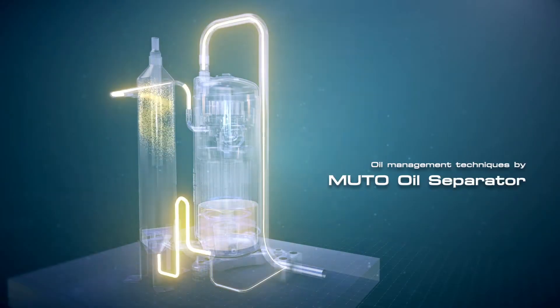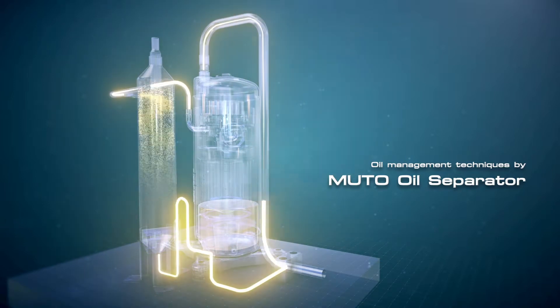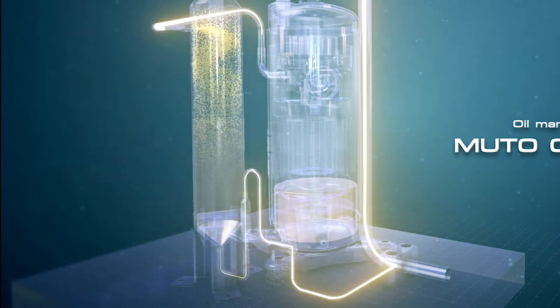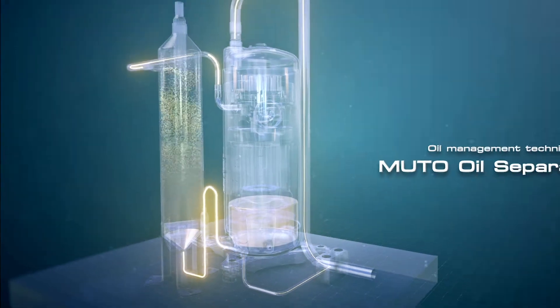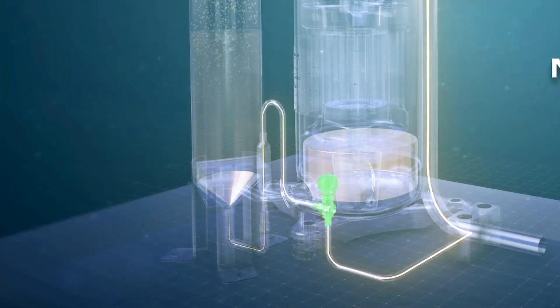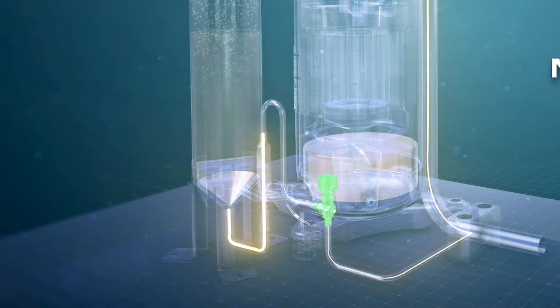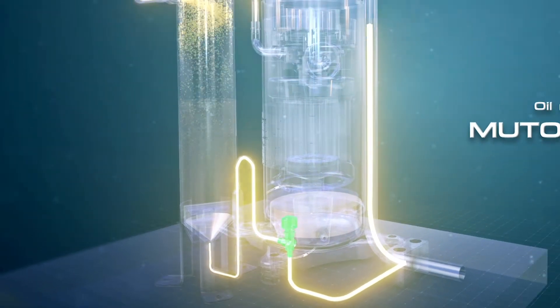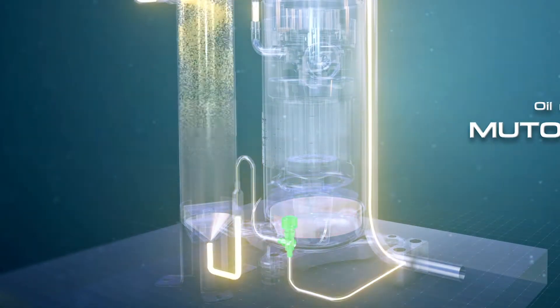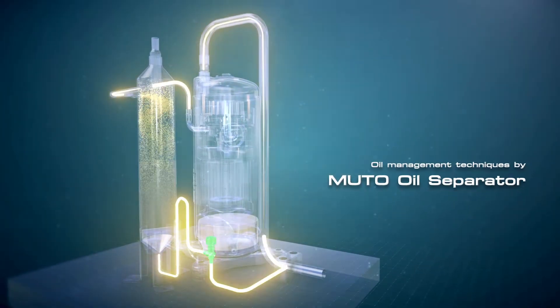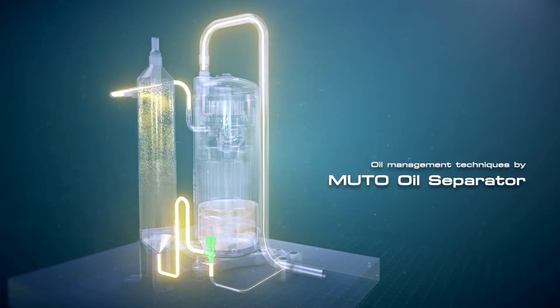Generally, when compressors run at high speed, a large amount of oil is released from the compressors. On the other hand, if compressors run at low speed, a small amount of oil is released. The oil return technique by MUTO oil separator keeps the oil level in compressors at a certain level by regulating the valve openings to match with compressor speed. In case of oil level decline to reach threshold level, the oil separator will promptly release oil into the compressor.